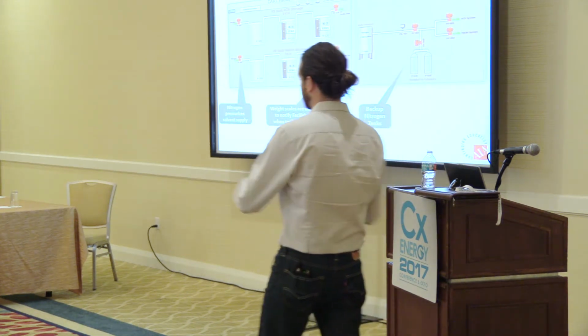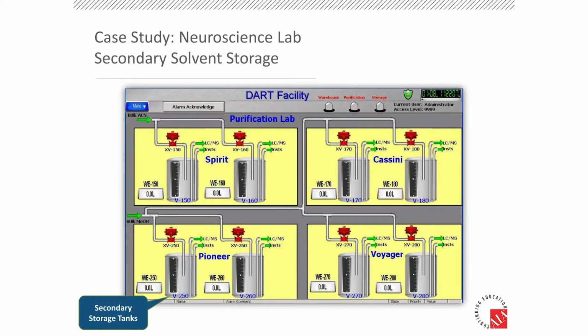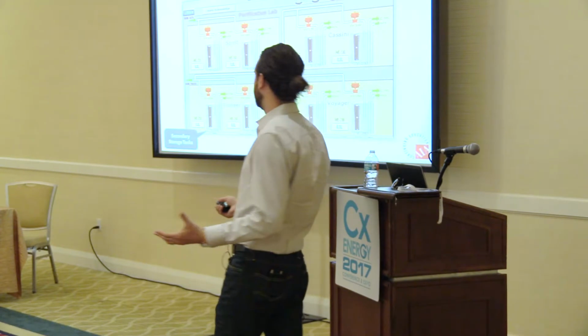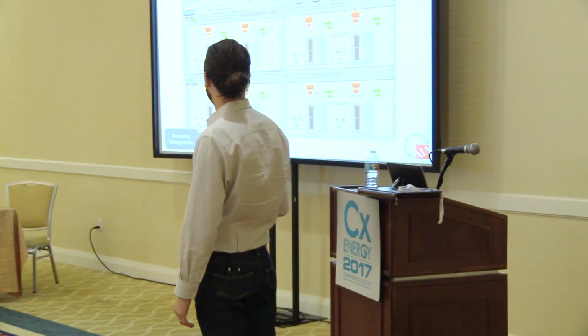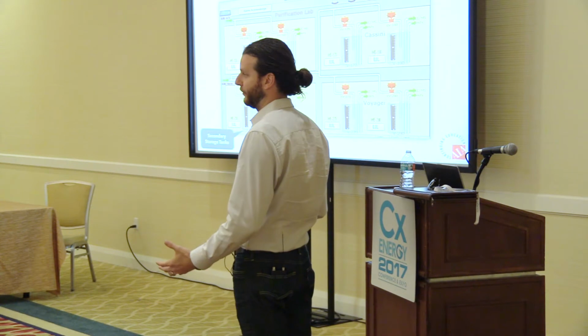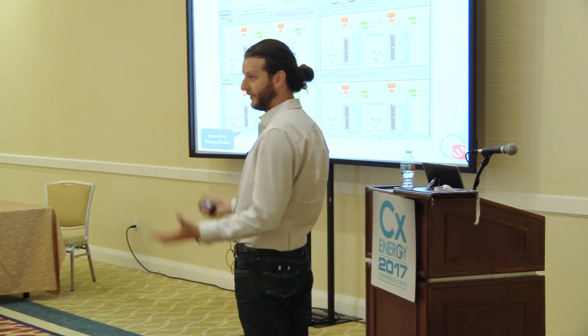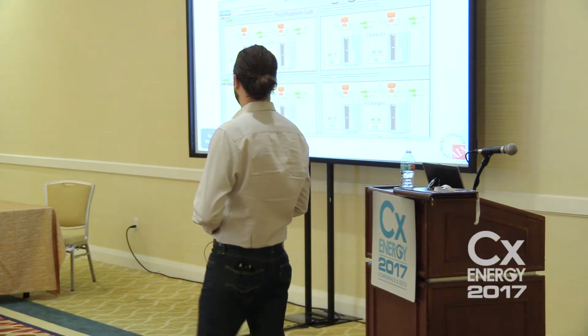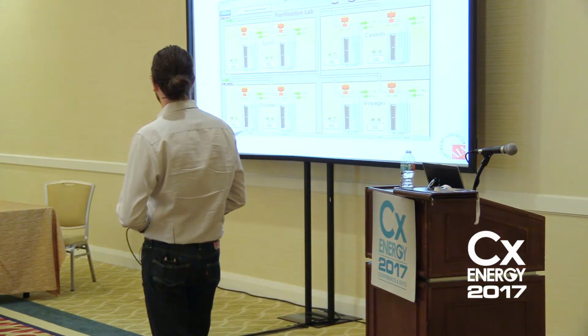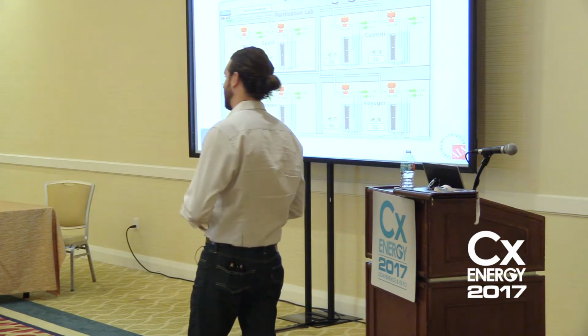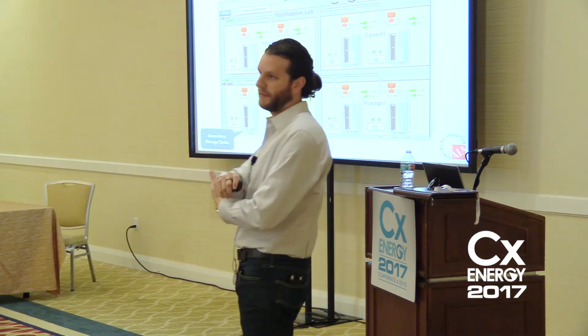So the supply system pumps into the actual laboratory. Within the laboratory, we've got these secondary storage tank systems, and basically there are 4 different tanks for different HPLCs, different laboratory benches around the space. These, again, have weight scales and leak detection systems within the cabinets, and these valves are used to modulate and maintain liquid level within the secondary storage tanks. It's an unpressurized system, so it's important that we maintain those tank levels, and in the event of a spillover, we have alarms and global shutdowns of the process, et cetera.